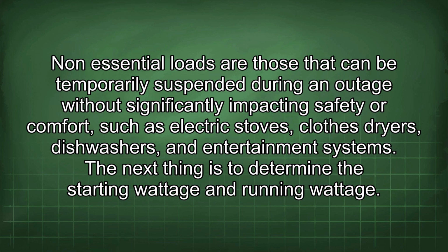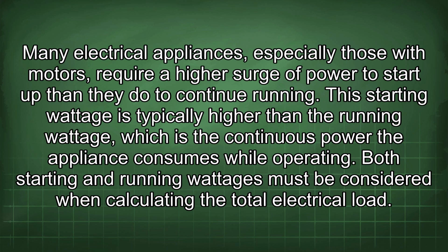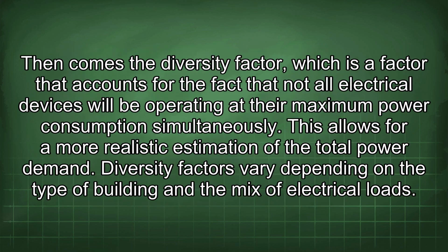The next thing is to determine the starting wattage and running wattage. Many electrical appliances, especially those with motors, require a higher surge of power to start up than they do to continue running. This starting wattage is typically higher than the running wattage, which is the continuous power the appliance consumes while operating. Both starting and running wattages must be considered when calculating the total electrical load. Then comes the diversity factor, which accounts for the fact that not all electrical devices will be operating at their maximum power consumption simultaneously. This allows for a more realistic estimation of the total power demand.